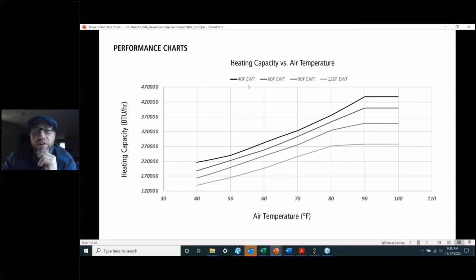So just to follow through on this point, you can see the capacity difference. If the entering water is 40, we've got about 45,000 or 450,000 capacity. And if that same entering water, with the same ambient condition, is 120 degree water coming into a 134A heat pump, we can see a really significant drop in output capacity. That difference in capacity at the same temperature is a direct hit to your COP. That difference in capacity means you've got to make it up with your compressor input energy, so you're going to take a really big hit. And so the takeaway here is that the reason to decouple the primary hot water heating load from the temperature maintenance load is that you really want your heat pumps to see really cold water. The colder the water to your heat pumps, the higher the capacity and the higher the efficiency.